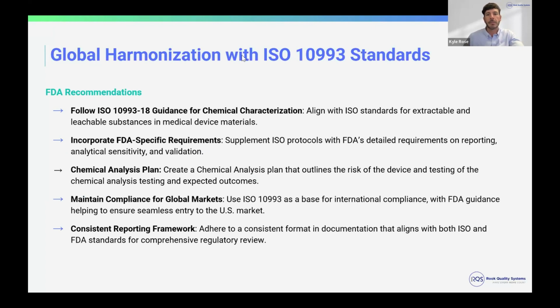Using both the standard and the guidance when you're going through this process, implementing the ISO protocols that apply for your device, creating a chemical analysis plan that outlines the risk of the device and the testing needed, maintaining compliance with global markets. So again, if standards get updated, making sure that you're aligning or doing a gap analysis to the new standards to make sure you're still in compliance, and then a consistent reporting framework as well. So making sure that both the ISO and the FDA guidance align on how these things should be reported within your design file and your technical files.